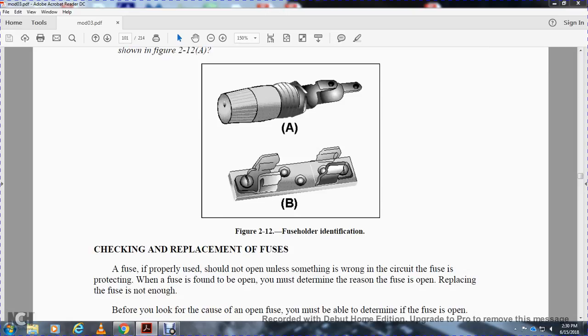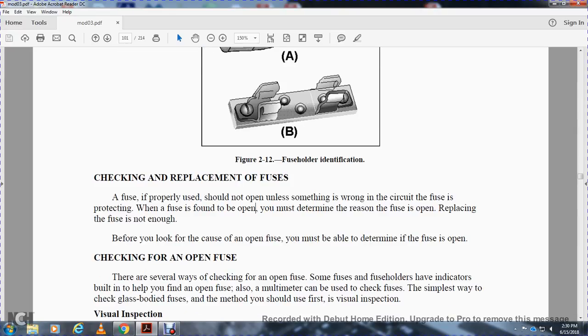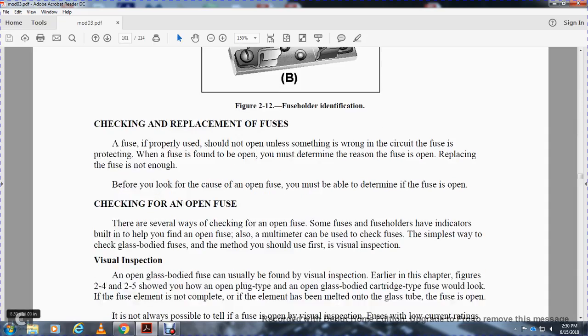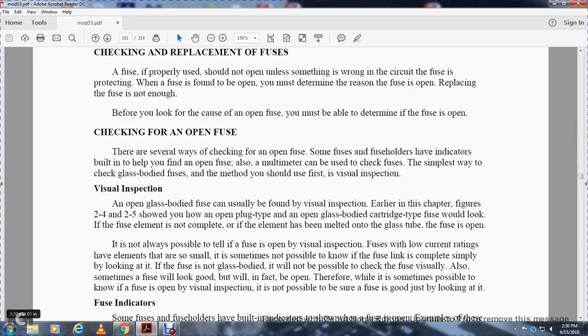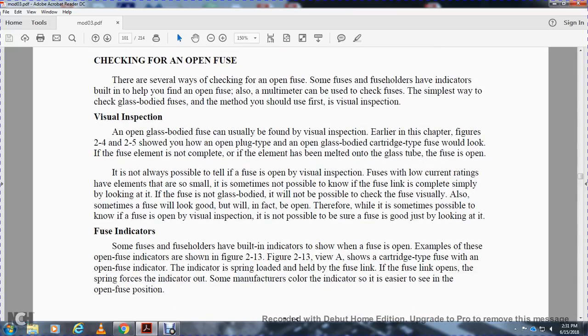Checking and replacement of fuses: a fuse should not open unless something is wrong with the circuit. When a fuse is open, it must be determined why the fuse opened. Simply replacing the fuse is not enough. Before you can correct the cause of the open fuse, you must be able to determine that the fuse is open. There are several ways to check for an open fuse. Some fuse holders have indicators built into them to help you find out if the fuse is open. For fuses with low current ratings, the elements are very small. Sometimes it is possible to see the fuse link and tell if it is open simply by looking at it. If the fuse does not have a glass body, it will not be possible to check it visually. Also, sometimes the fuse will look good but in fact be open. Therefore, it is not always possible to know if the fuse is open by visual inspection.